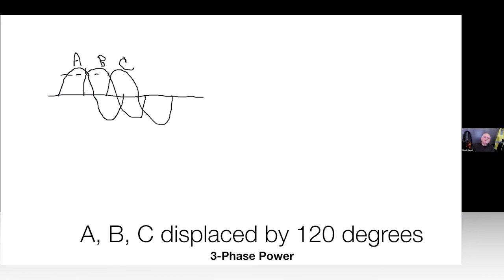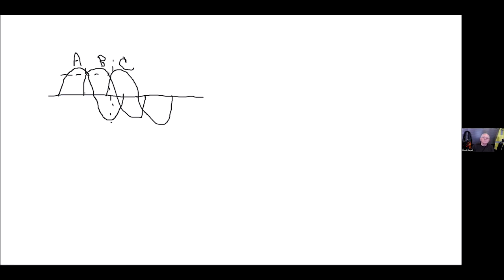If I were to freeze those sine waves at some point in time, all three occurring 60 times a second, I'd have some voltage from C-phase, some from B-phase, and quite a bit from A-phase. Without getting into all the math, what we do is multiply the phase value by 1.732, which is the square root of three. This is where our voltages come from. If I have a 480Y/277 system — which is how the code tells me to express that system — I have a Y-connected transformer.